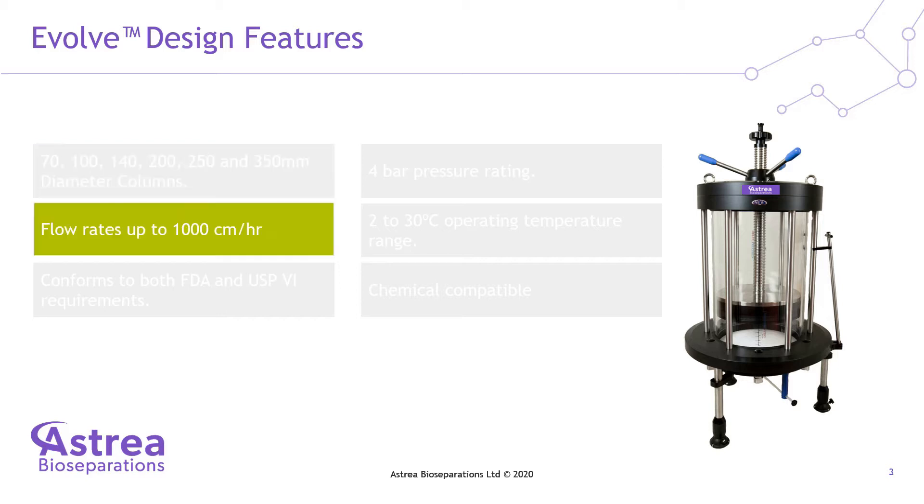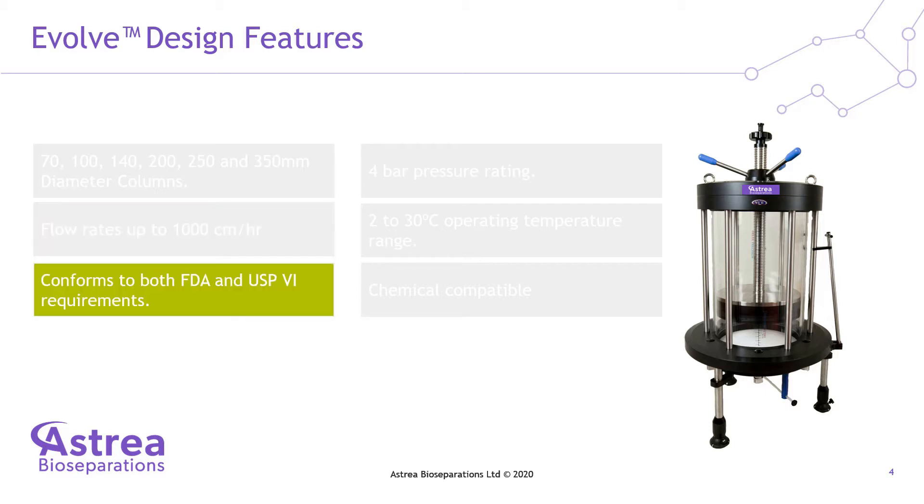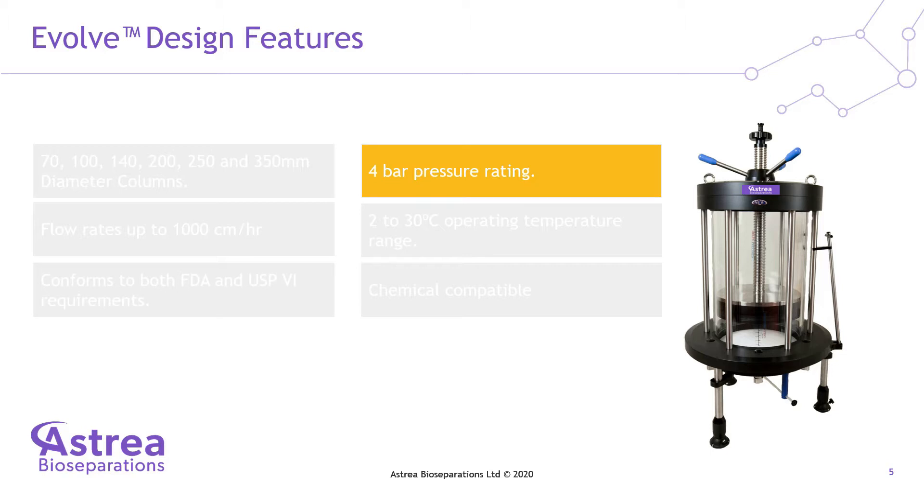The design features include high performance, cost effective and scalable technology, efficient flow distribution, easy to use and low maintenance. The column is a pharmaceutical grade acrylic column with a non-metallic flow path, eliminating the risk of any corrosion of the wetted flow areas, and is suitable for use with a wide range of chromatography media types including Astrea's extensive range of affinity separation products.